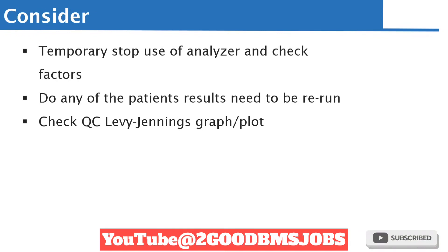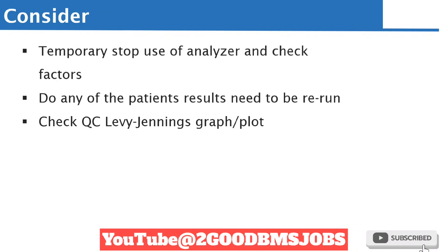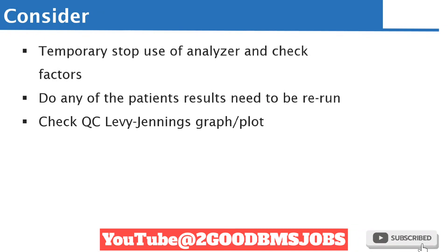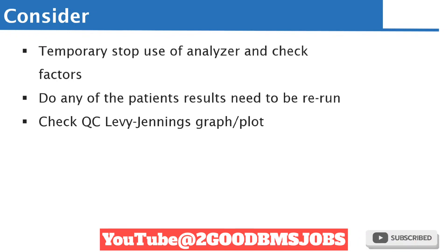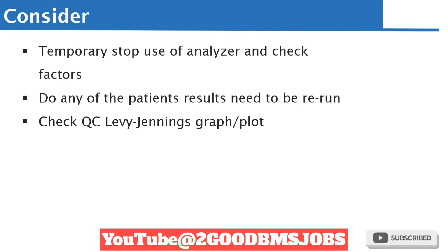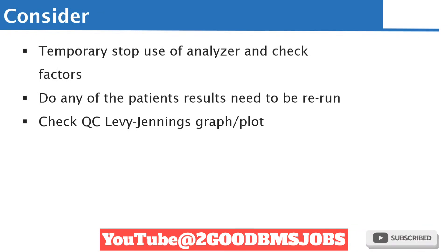You may also need to consider whether there is a possibility of re-running any patient sample that has possibly already gone through that analyzer. Then another thing you need to consider — before even starting your investigation — is to check your Levey-Jennings graph or plot.